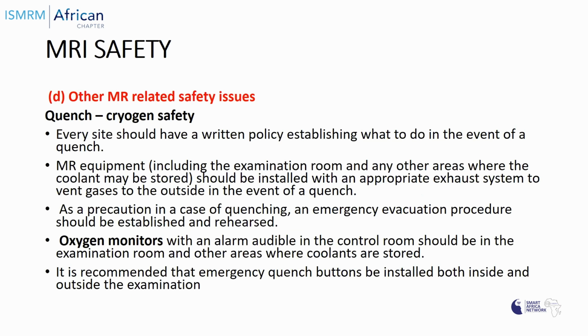So every site should have a written policy establishing what to do in the event of a quench. MR equipment, including the examination room and any other areas where the coolant may be stored, should be installed with an appropriate exhaust system to vent gases to the outside in the event of a quench. As a precaution in case of quenching, an emergency evacuation procedure should be established and rehearsed by every MR facility.